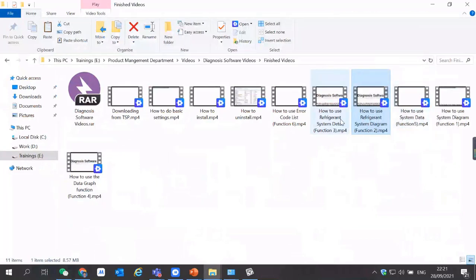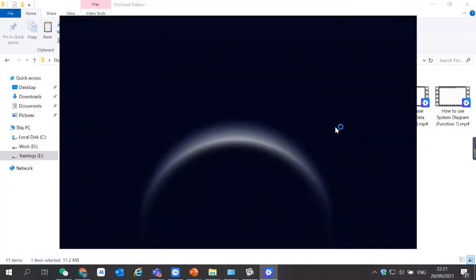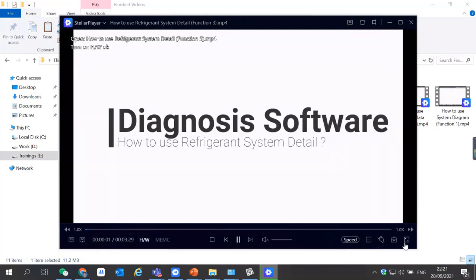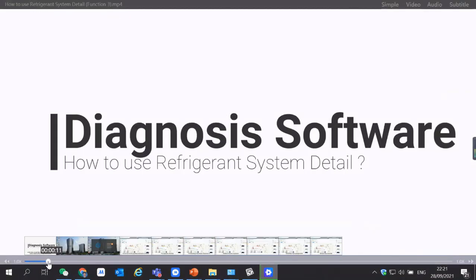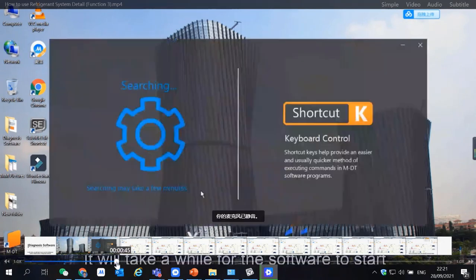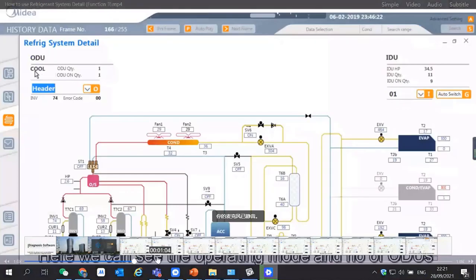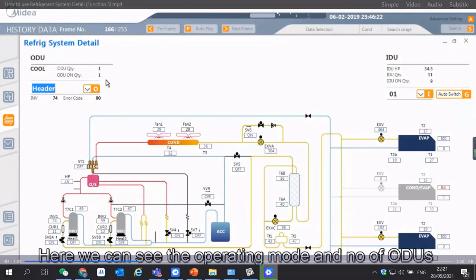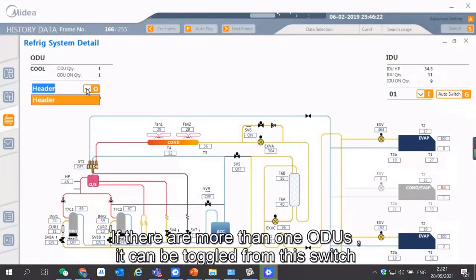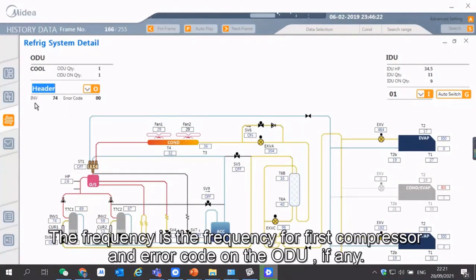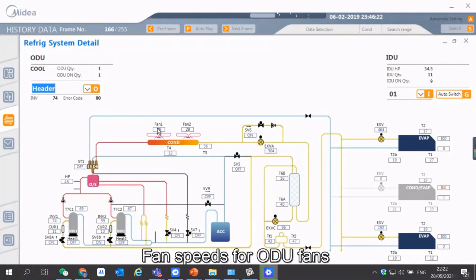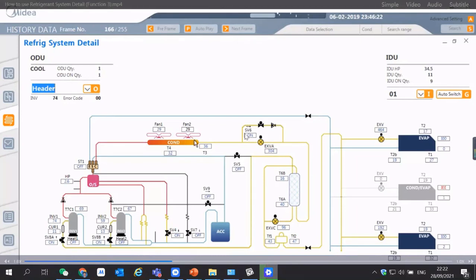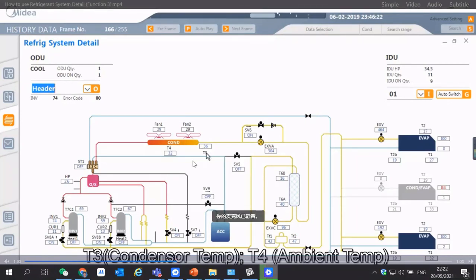This one we call refrigerant system detail. This function shows more detailed parameters about the ODU side. So I go directly to the function; entering the diagnosis software is the same. So here is the ODU, and here you can see very detailed parameters about the ODU parts: the frequency of the compressor and the fan speed of the ODU fans, the switch valves open or closed, and the condenser temperature, ambient temperature, and sensor values, right?